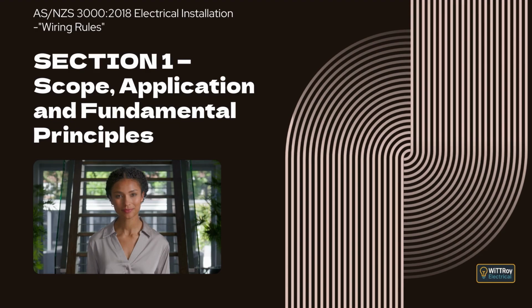Clause 1.9.4.2 Acknowledgement by the owner or operator. If a design does not follow Part 2, the owner must formally acknowledge this so everyone understands the approach and the safety decisions taken. Clause 1.9.4.3 Documentation by the designer. The designer must record the reasons for not using Part 2, the checks needed to make sure the installation is safe, and any special instructions. This documentation shows how the design meets the aims of Part 1. Clause 1.9.4.4 Verification. Before the installation is used, all parts covered by the special design must be tested and inspected to confirm they actually meet the required safety level.